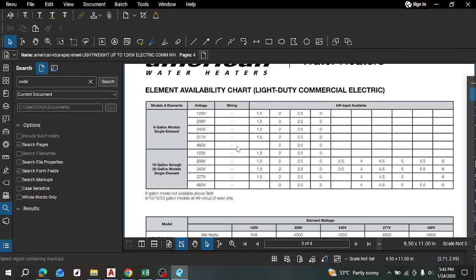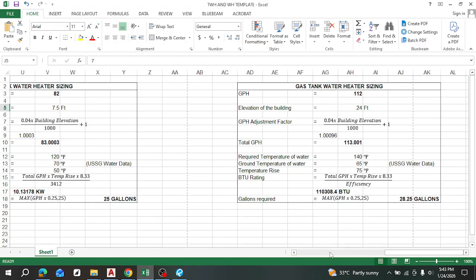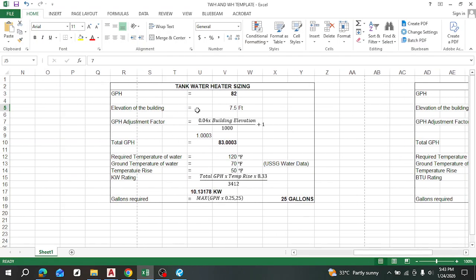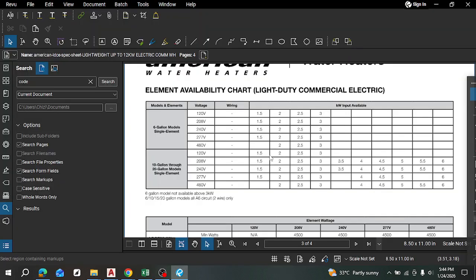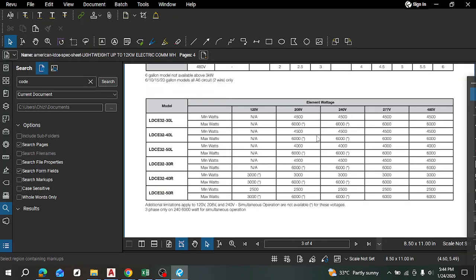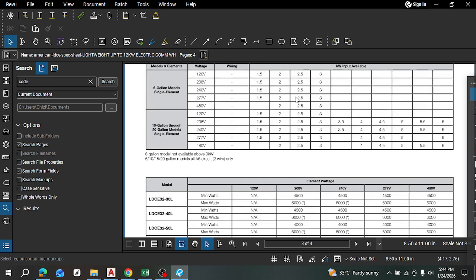So you check here, you see that for this one it is way less. Mostly this is the highest, 6 kilowatts. And what you are looking at here for the tank is about 10, right? So either we take two of that, or we just go higher and see if we can find something that can take even more. It's based on the elements, that's why it's modular, one by one, right? So maybe the minimum size is 4. Okay, these are the minimum sizes, and then it's in multiples of this, right?